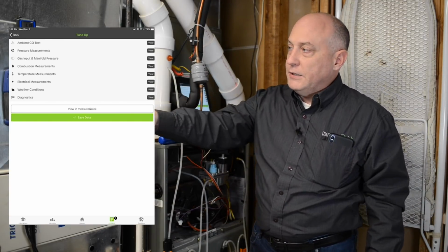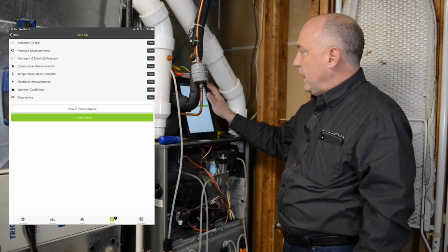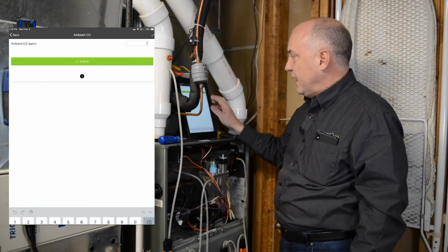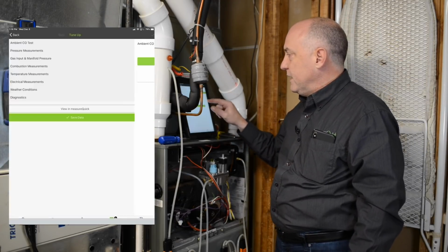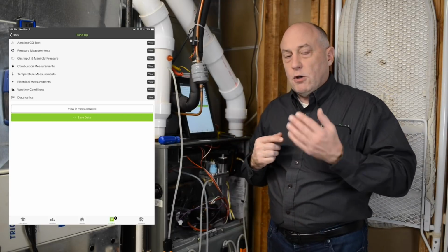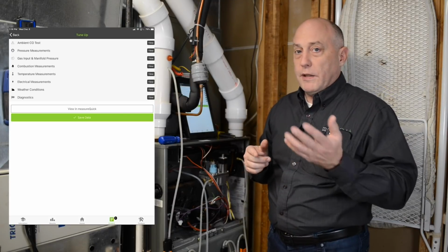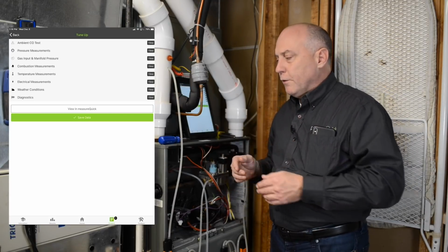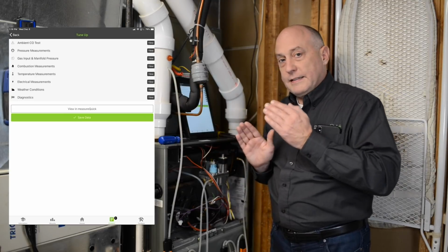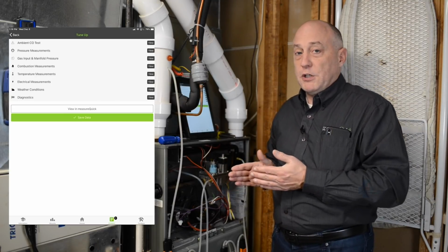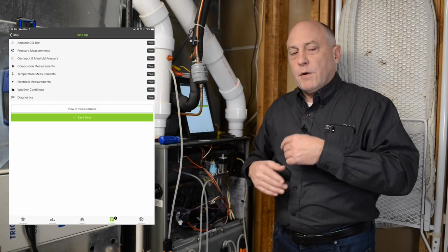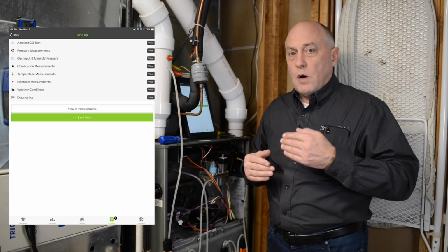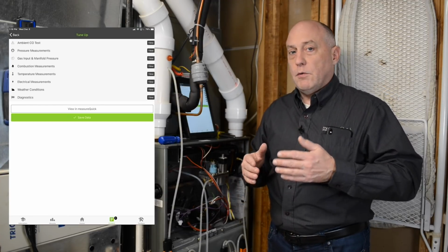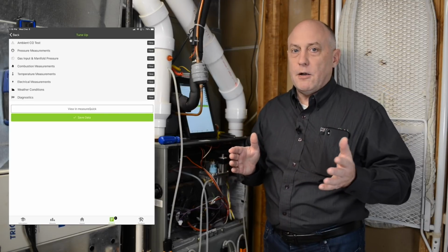So I have the analyzer turned on, I have it zeroed out, but I'm going to go ahead and, in my ambient CO test here, just enter in 0 parts per million and hit submit. Now I can also activate my BluFlame and pull that in off the BluFlame, but the first go around here, what I want to do is get the furnace set up. I want to set the gas pressure to nominal 3.5. Then we're going to go out and clock the meter and it'll walk us through where to set the fuel pressure, and we'll do our combustion analysis and set up and get all that running.